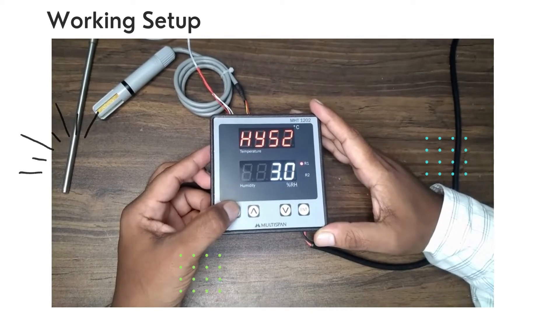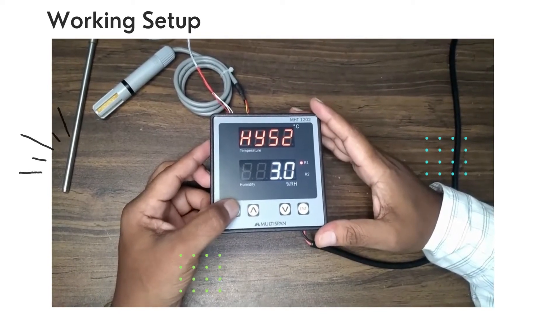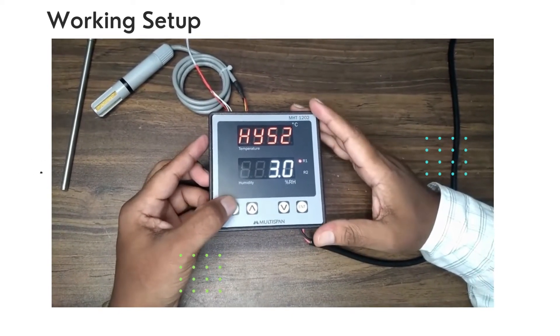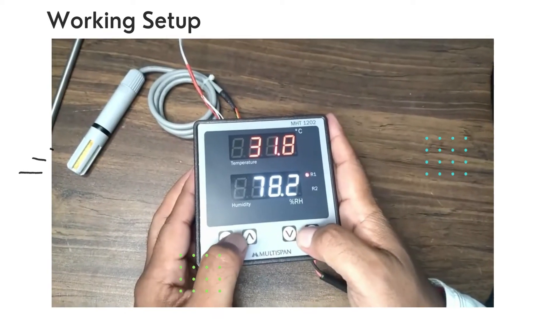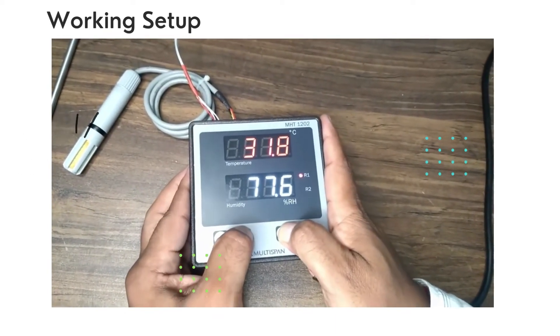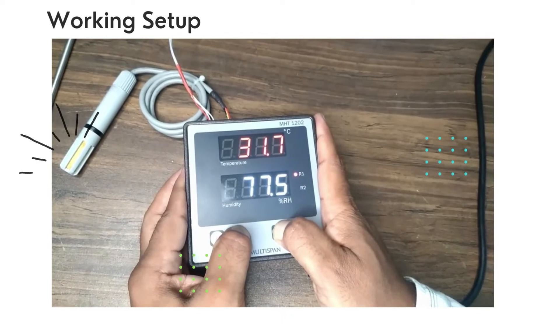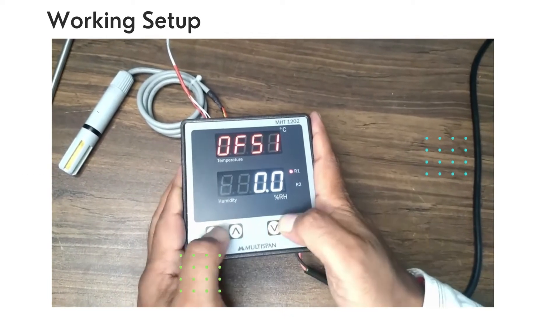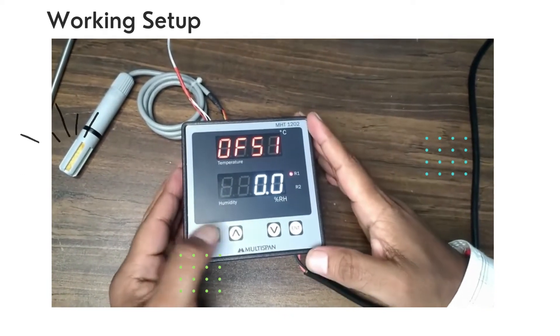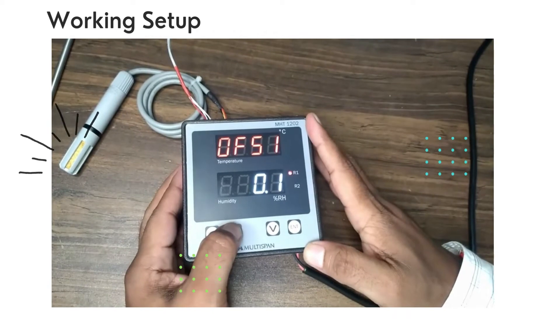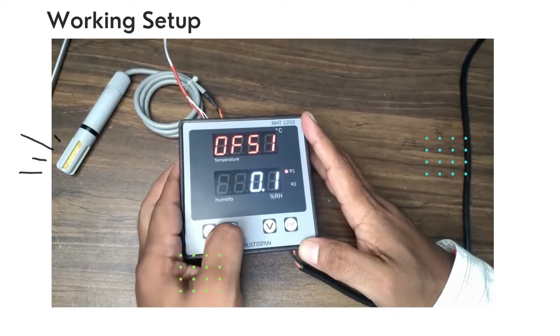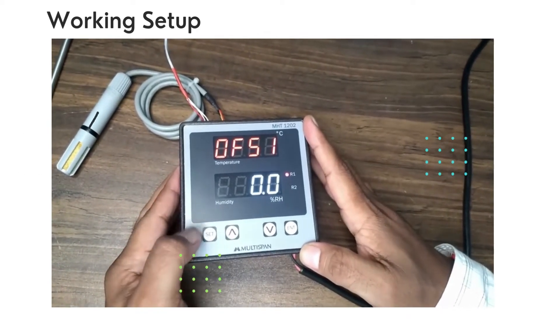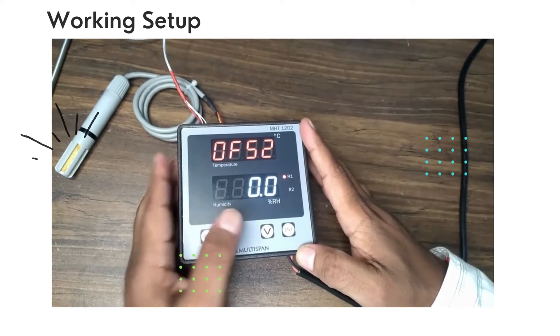Now if you want to do calibration or put any offset according to your use, then press Up and Down keys together. You will enter into Offset Point 1. Now here you can set the offset value. Now press the Set button. You will get Offset Point 2 where you can set zero and span accordingly and do the calibration.